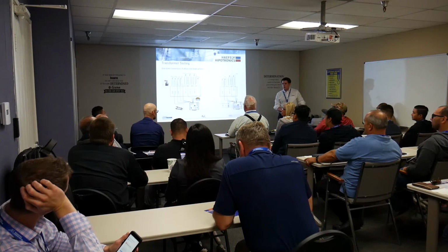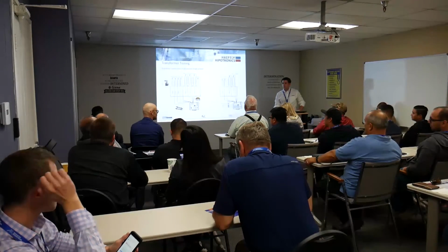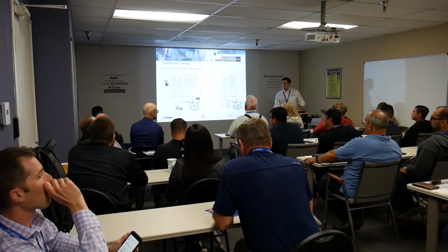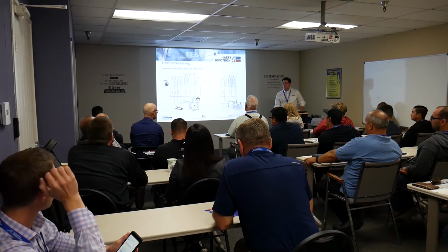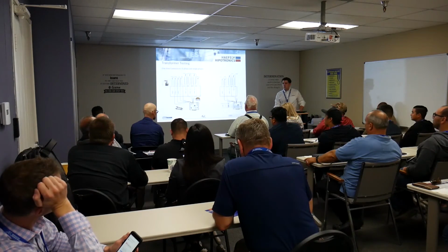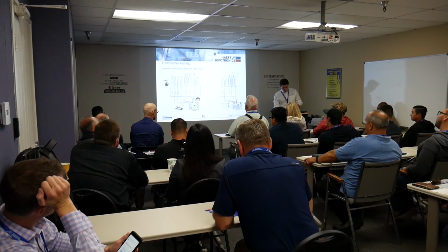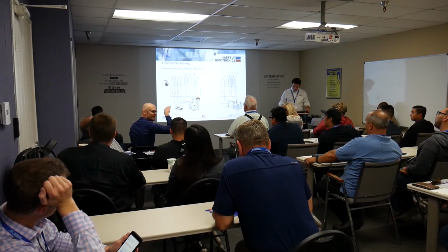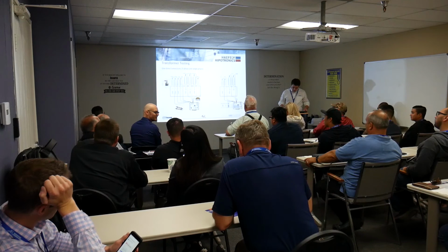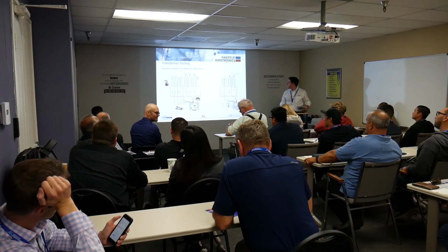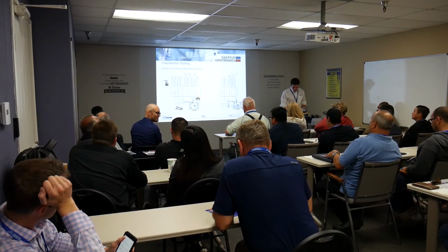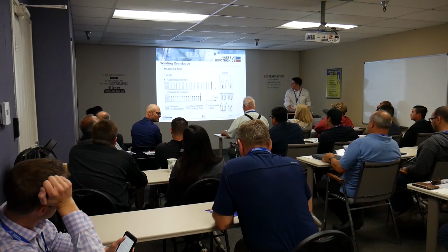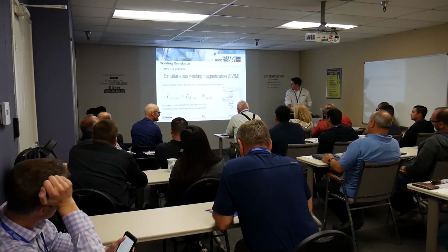Okay, so this is configured for both winding resistance and turns ratio. Yes. I was just wondering, because depending on the turns ratio, it can create quite high peaks if you inject on the low side, depending on what your test device is injecting. I think this is a DC test, right? This is DC. Yeah, but you always have a pulse when you switch on the source. Somehow you need to establish the current, so at some point your source is switched on. So you always have a di/dt.